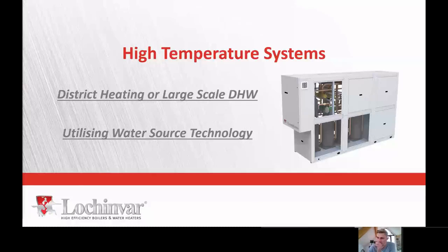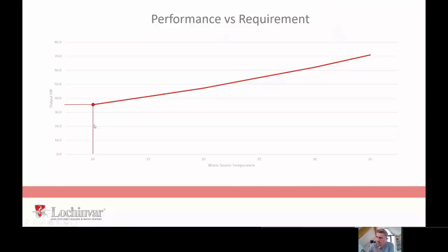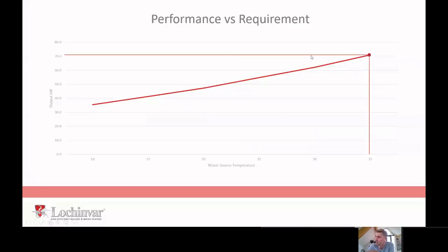Okay, so a water source heat pump. This is the heating curve from a water source heat pump. At a 10-degree source temperature, we're looking at 35 kilowatts. At a 35-degree source temperature, we're looking at 70 kilowatts in the water source heat pump. Now, the interesting thing about this is that the input to that water source heat pump always stayed the same. Its absorption capabilities with that source temperature went up and up and up very quickly.